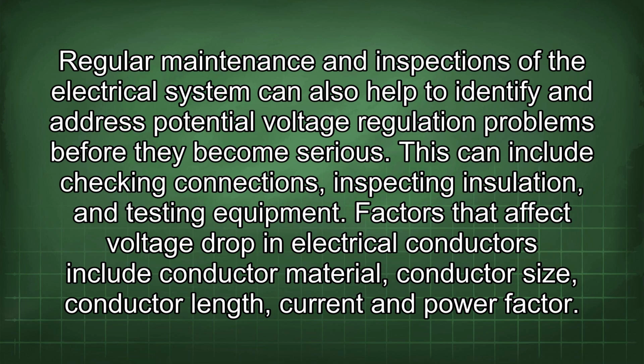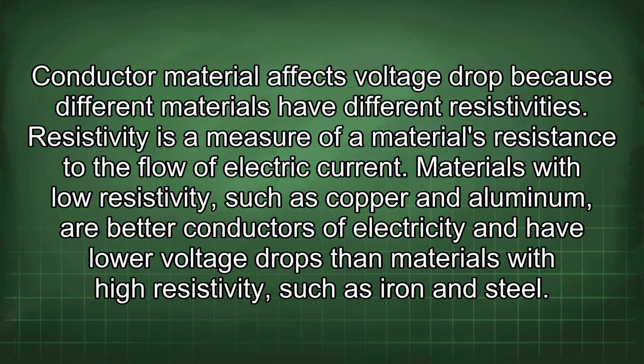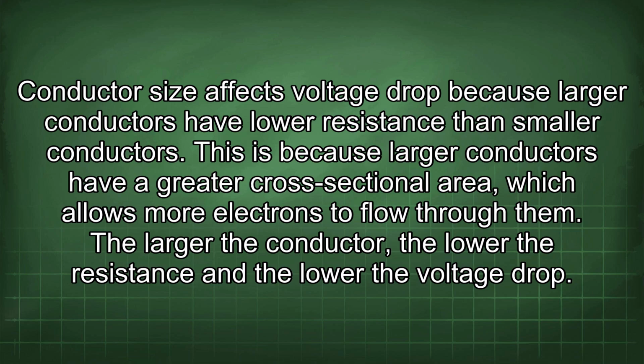Factors that affect voltage drop in electrical conductors include conductor material, conductor size, conductor length, current, and power factor. Conductor material affects voltage drop because different materials have different resistivities. Resistivity is a measure of a material's resistance to the flow of electric current. Materials with low resistivity, such as copper and aluminum, are better conductors of electricity and have lower voltage drops than materials with high resistivity, such as iron and steel. Conductor size affects voltage drop because larger conductors have lower resistance than smaller conductors.